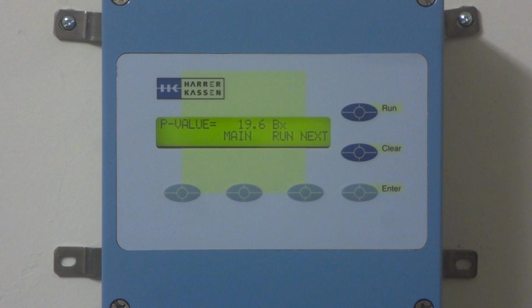it will not always be exactly the number that you put in. So we might have to adjust it, and often have to adjust it afterwards. But as you can see, this one's going to be very, very good. Very close. The number is stabilizing at 19.9. If 19.9 is the final number, we will show you in the next section how to adjust the offset in order to make it 20.